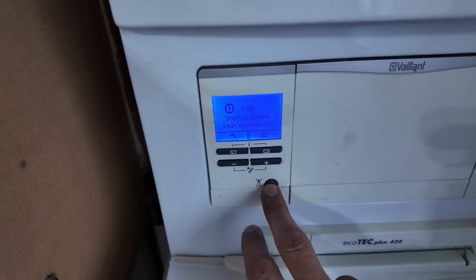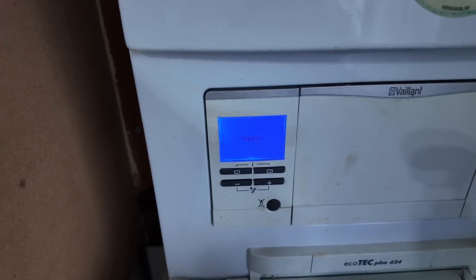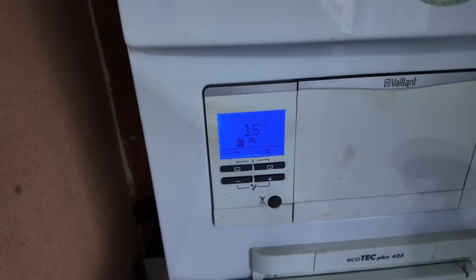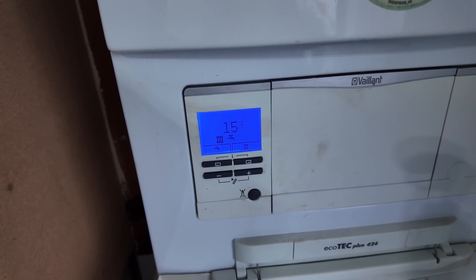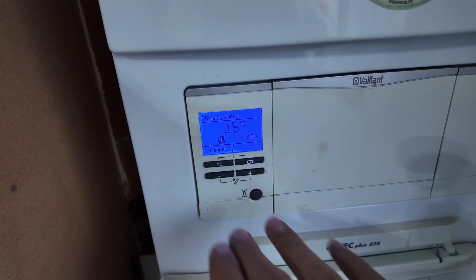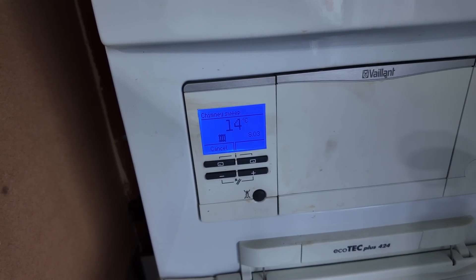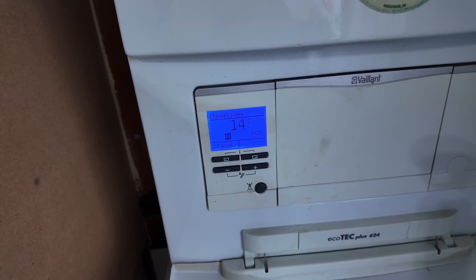We've got F28 on here. Let's do a reset — clear faults. The tenant said it runs for about 20 seconds and then shuts itself off. I don't know if the demand is calling at the moment — let's just put it in chimney-sweep mode. It's not hot water, it's nothing. It's stuck on S3, so it's not going to ignition. I can hear it sparking inside. Let's take the case off and see what's going on.